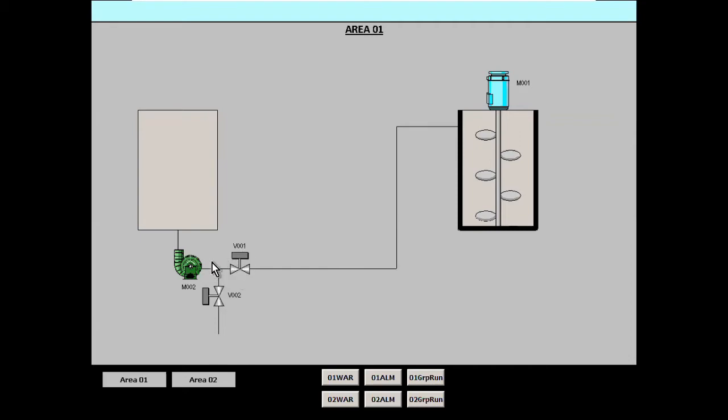Especially in this instance, you would want to have confirmation that it is closed. Open doesn't matter, but if it's not closed, you know it's got a path through it. And this one is a different one. You would want to make sure that the drain valve is closed, so you don't pump everything to drain. So if it's not closed, it would technically be open. But yes, let's put both limits on.